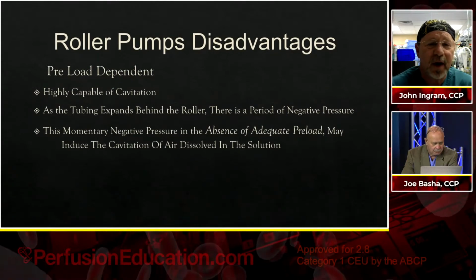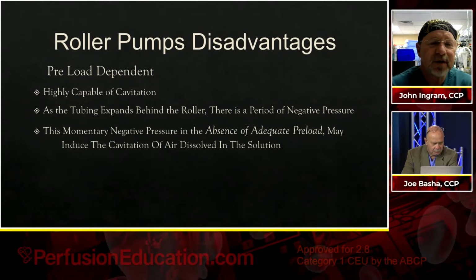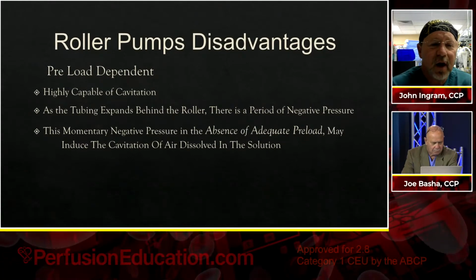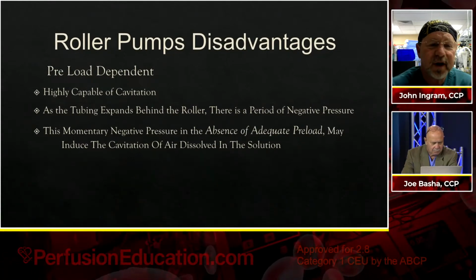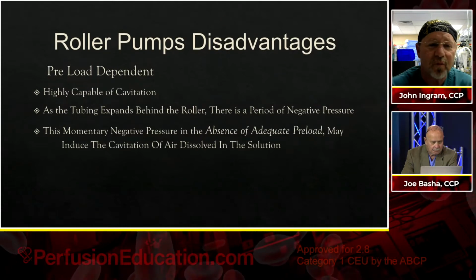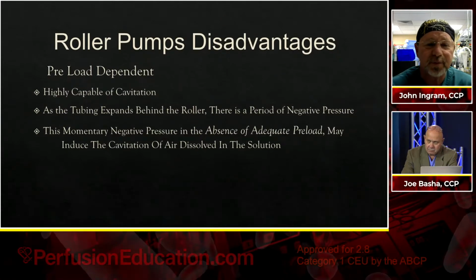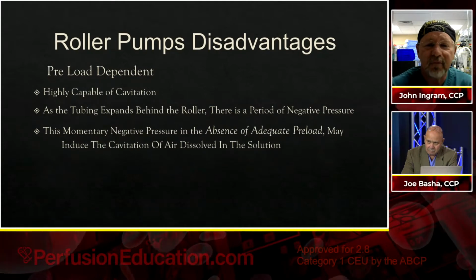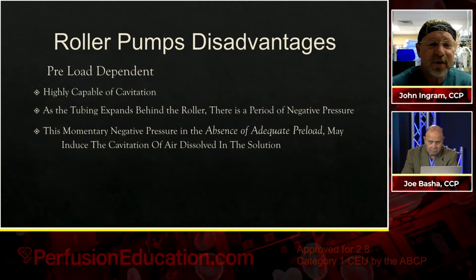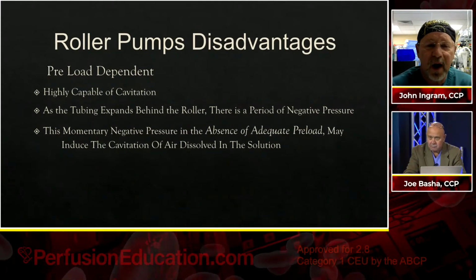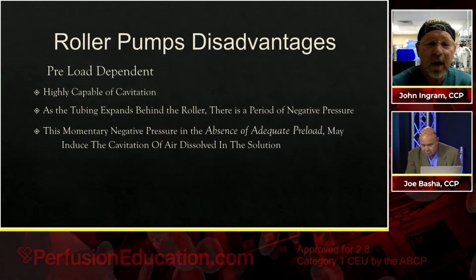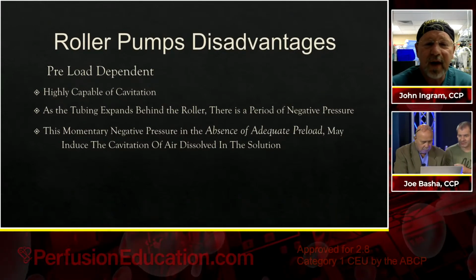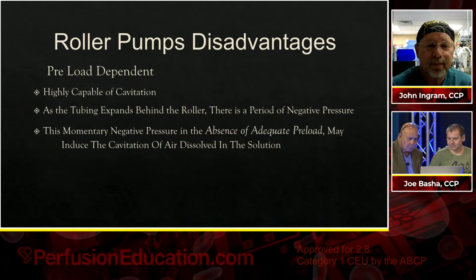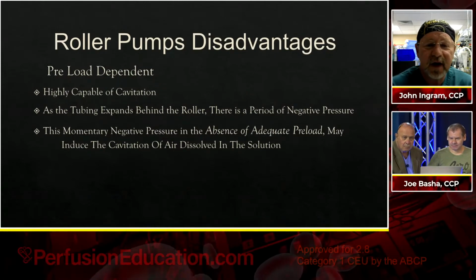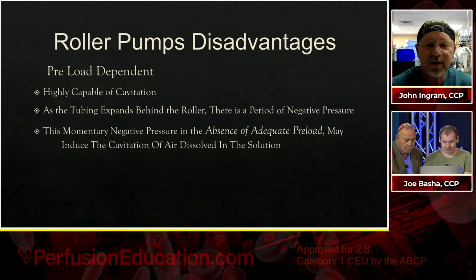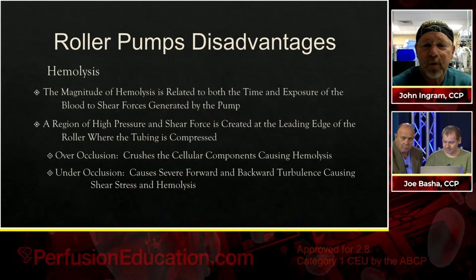There's a preload dependent that's a disadvantage because it's highly capable of cavitation. Now, as the tubing expands behind the roller, as the roller is going through the pump and the tubing is being compressed, there is a period of negative pressure. This is a momentary negative pressure right behind the roller. It's a momentary negative pressure in the absence of adequate preload. And it may induce the cavitation of air dissolved in the solution. You guys hear me okay?